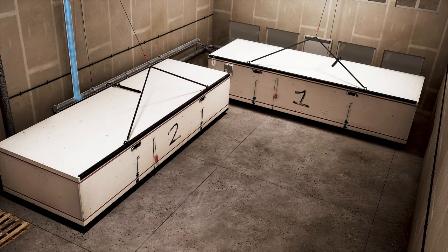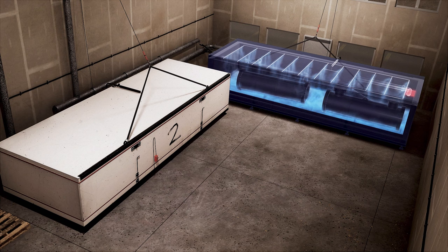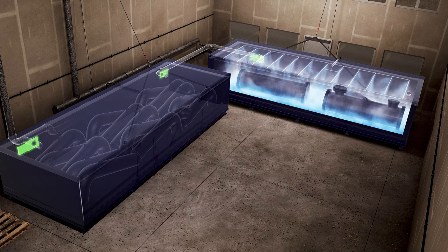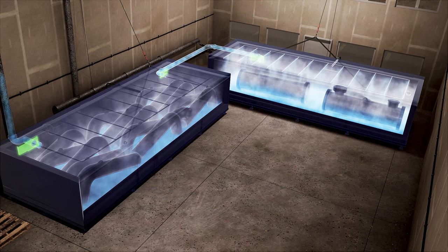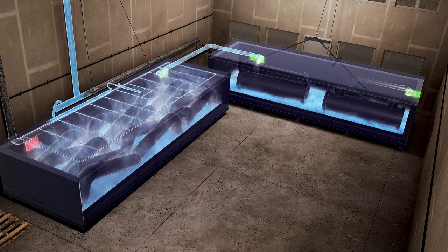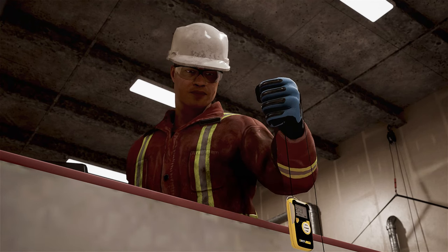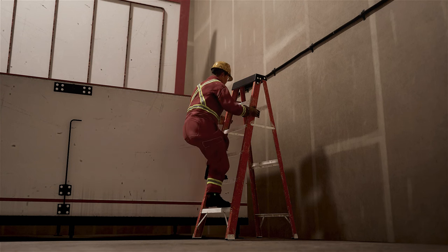During the cooling process, nitrogen is supplied to one cooler, and its exhaust gate valve is closed. The gate valves are open in the transfer duct between the coolers, as is the exhaust duct on the other cooler. This flow path exposes the other cooler to nitrogen, partially cooling its contents as the gas moves out of the system. This pre-cooled pipe is then fully cooled during the next overnight treatment cycle, when the nitrogen flow path is reversed. When a cooling cycle is complete, the nitrogen is purged using compressed air, and a gas monitor is lowered into the cooler. Once a safe level of oxygen is confirmed, workers can climb into the cooler to unload the equipment.